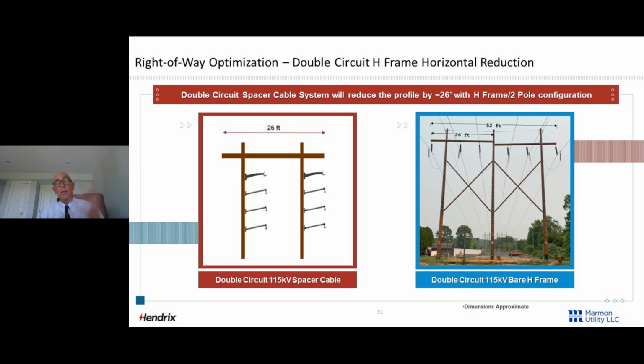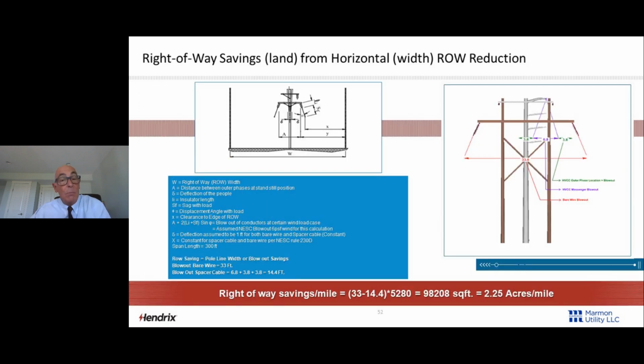How about a double circuit? Double circuit on an H-frame. You don't want to put it on the same pole. You want to put it on 2 poles connected with an H-frame. Now you're saving 26 feet. Spacer cable, 115 kV versus bare wire. Massive, massive savings. Okay, so what are we allowed to say we're saving?